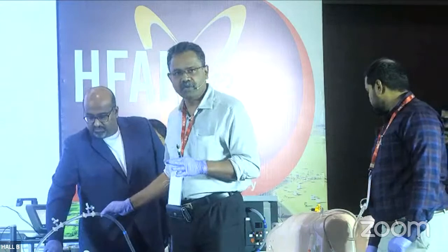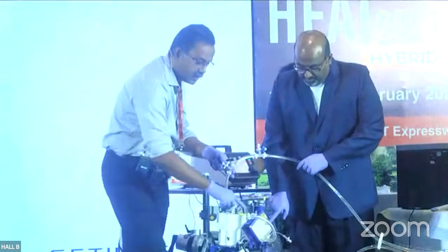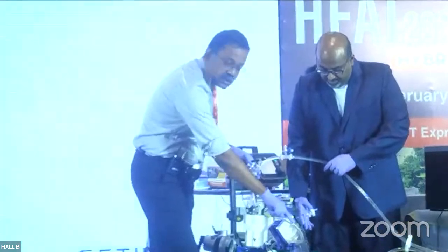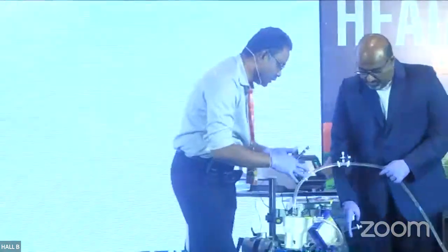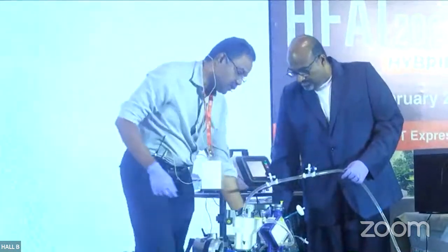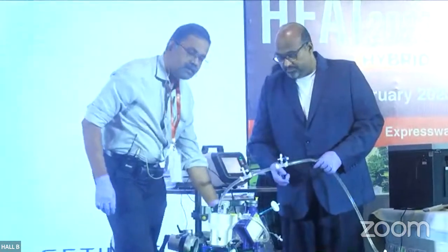That is the pre-membrane, pre-pump pressure, before the pump. That is P1. Next is P2. From the pump, the blood goes here and here, and from here it will be a higher pressure. This is before the oxygenator, called the pre-oxygenator pressure. And after the oxygenator, this is the post-oxygenator pressure. So we monitor this as P2, and this is P3. The pre-oxygenator pressure is P2, and the post-oxygenator pressure is P3.